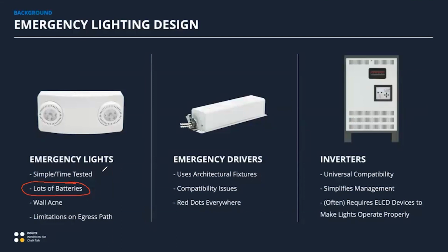Now, people think self-diagnostics gets you totally away from this obligation. That's not true—there's still a documentation step necessary. Even with self-diagnostic emergency lights, someone still has to go around every month and say, 'oh, fixture 102, that one has a green LED, it's good to go.' If the fire marshal comes in, he's going to need to see that.